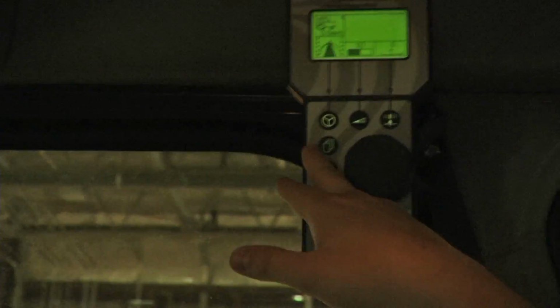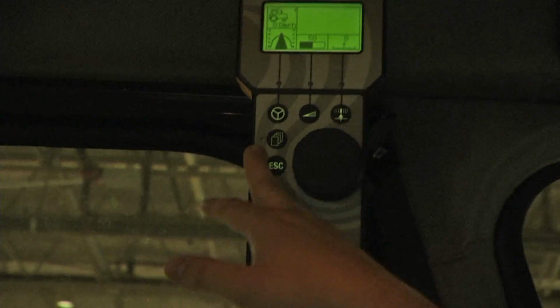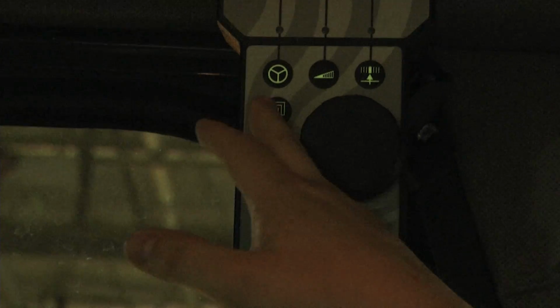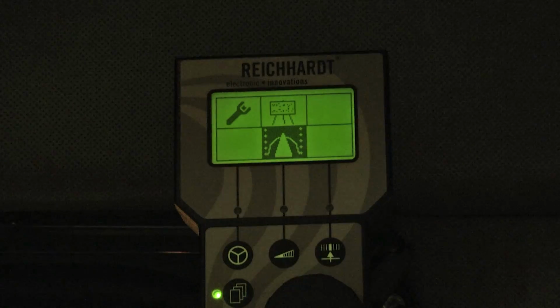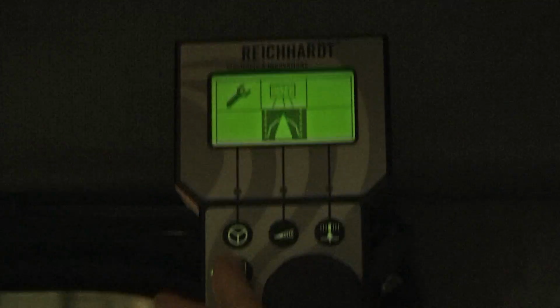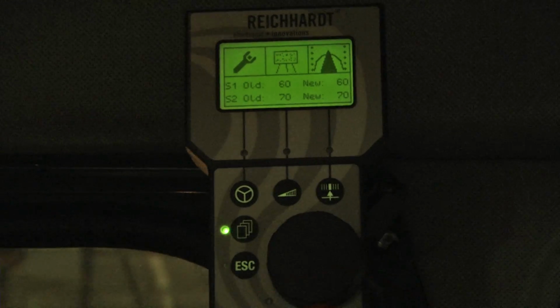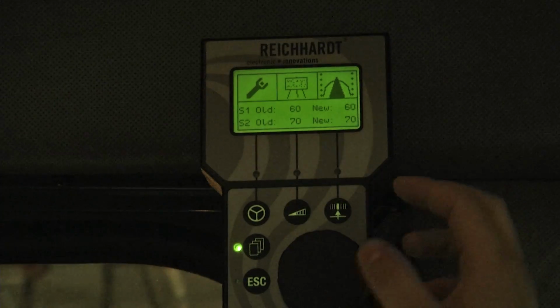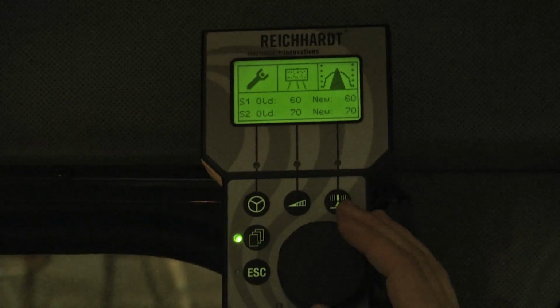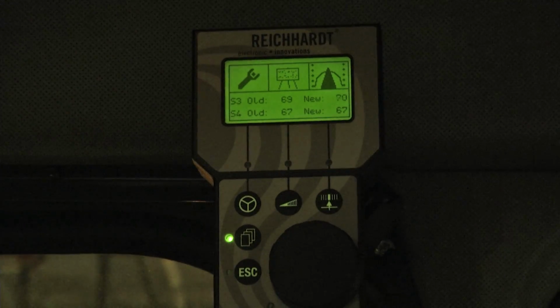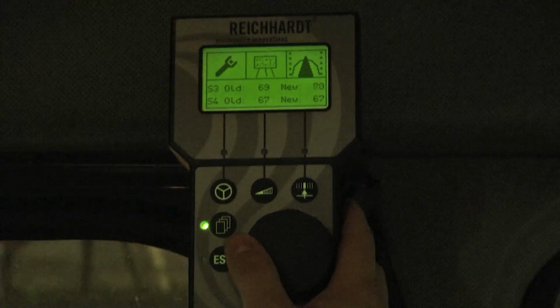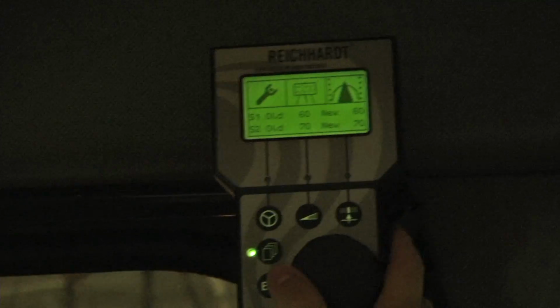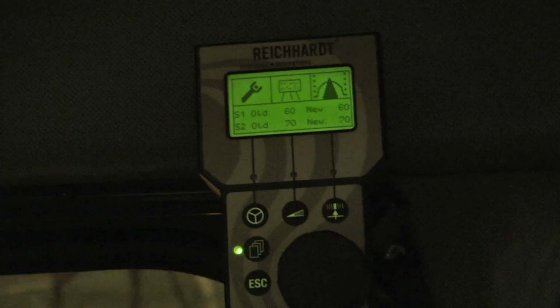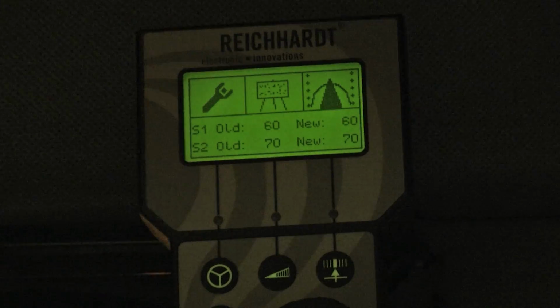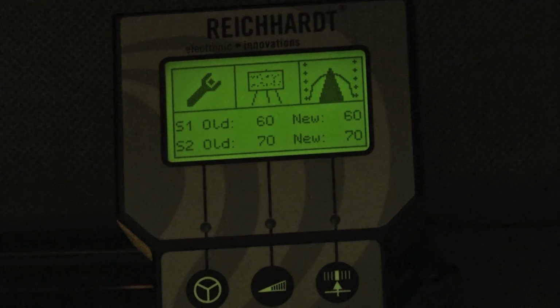This icon that looks like 3 pages stacked up on top of each other is our menu. If I just tap this menu, it's going to take me to the icon for the Tach sensor. If I tap the menu button again, I'll go into this menu, and you'll notice I have new and old readings, S1, S2, and if I turn the dial, S3 and S4. The new value is the current reading of the sensor. The old value is the stored previous calibration. So if these numbers match up pretty close, you wouldn't need to recalibrate it.